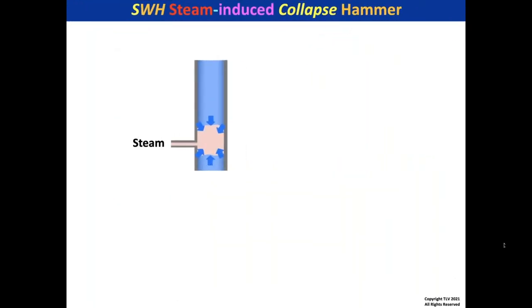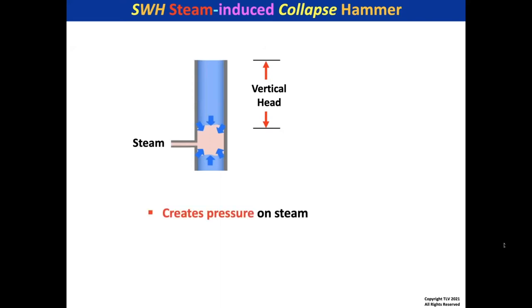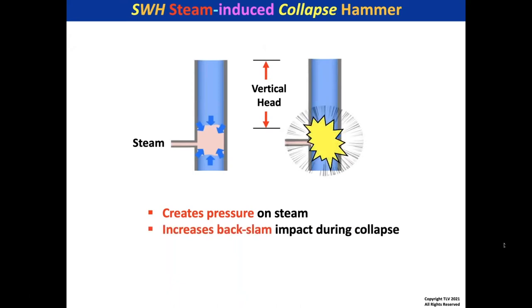Now let's look at a vertical line at the base of the riser. Flash steam comes in and makes a pocket right at the base of the riser. With 30 to 40 feet of vertical head, plus 25-pound back pressure in a return header, that creates a lot of pressure on that steam pocket. When that pressurized pocket collapses, it can create a tremendous back-slam impact. We mitigate trap damage by installing a check valve after the trap.